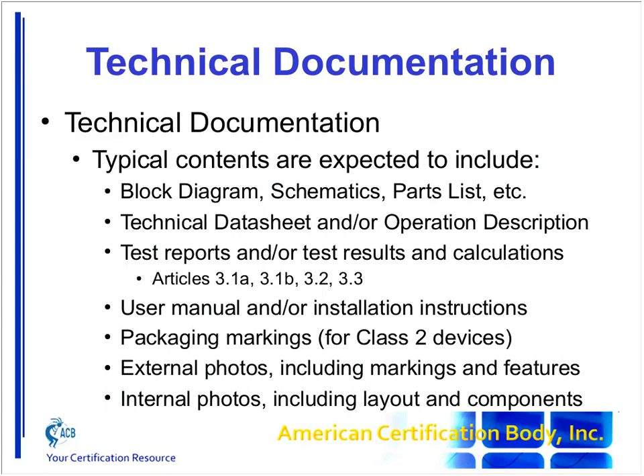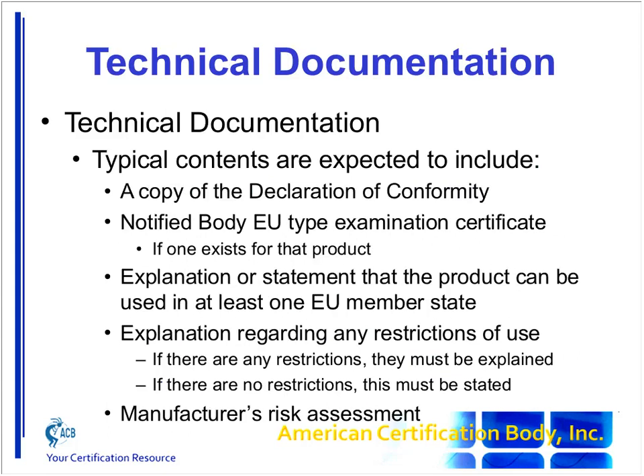The notified body certificate, if such a thing exists for your product. An explanation or statement that the product can be used in at least one EU member state must be within your technical documentation, and an explanation regarding any restrictions of use. So if it's a Class 2 device with restrictions of use, then you'd need to explain what the restriction is. For example, 5 gigahertz Wi-Fi, indoor use only. And if there are no restrictions at all, then that also must be explained and detailed in your technical documentation.